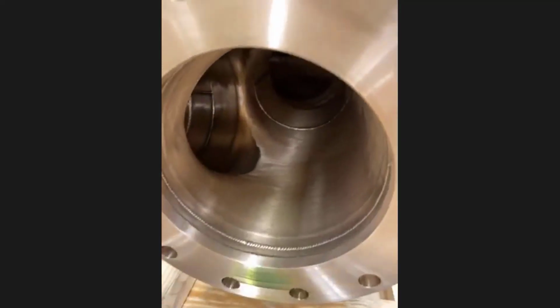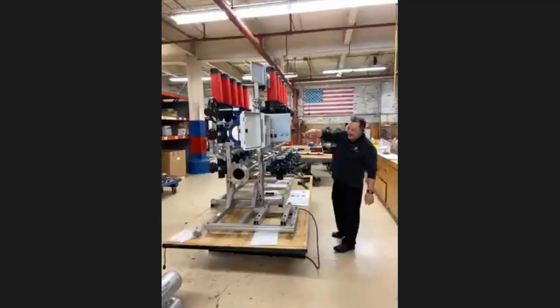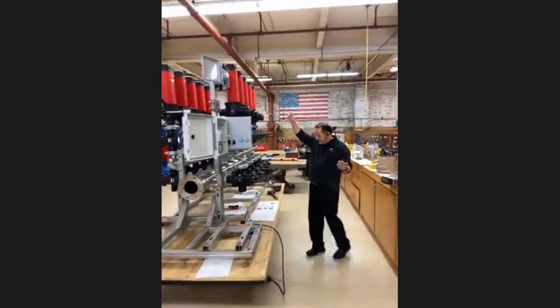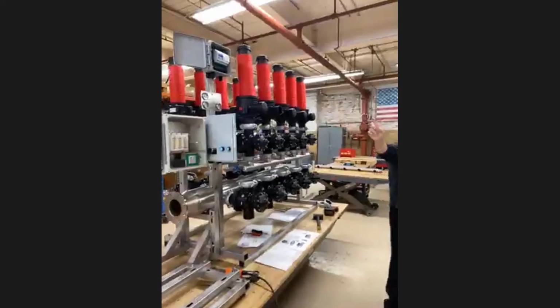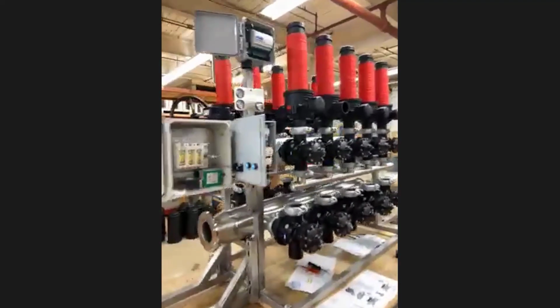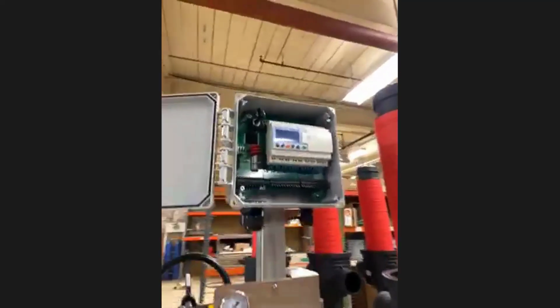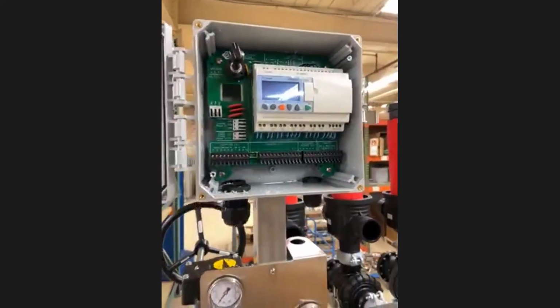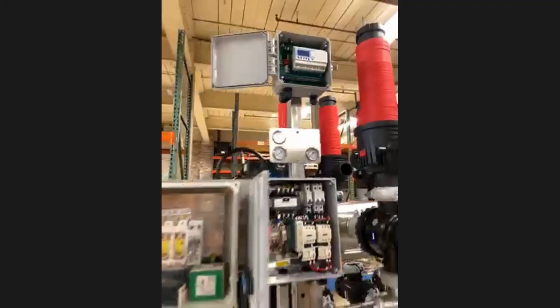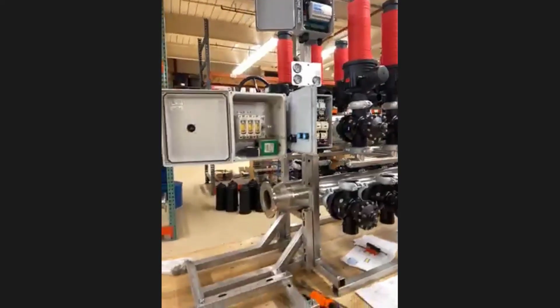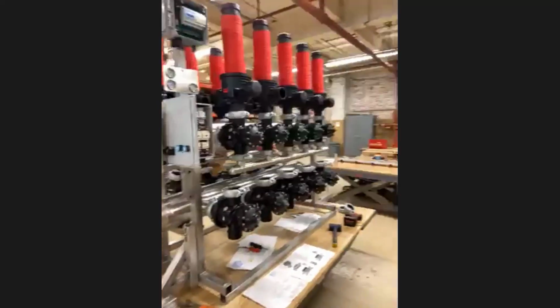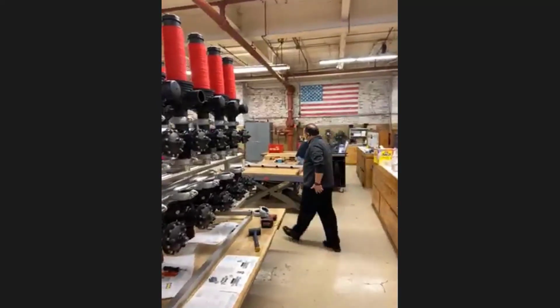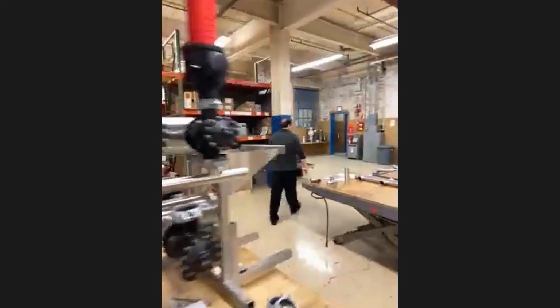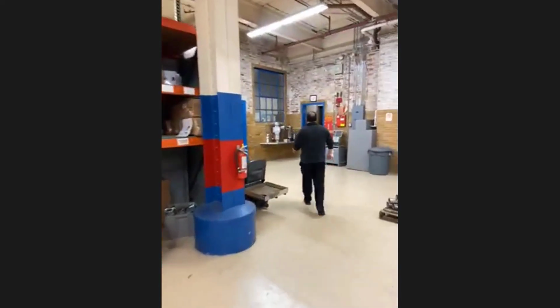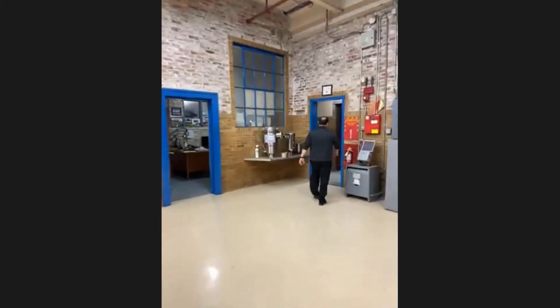And then this unit right here is another Turbo Disc unit, another 10-pod unit. It has a disconnect on it. You can come over here and see the Maxim controller. The Maxim controller is what's normally provided on these units. It'll have a nice plate on there that says Maxim. I'm just showing you the inside right now. The motor starters are all UL, and this one has a disconnect for this Turbo Disc, and they're putting that together right now. And then we'll move upstairs. If you want to ask a question now, that would be great as I walk.